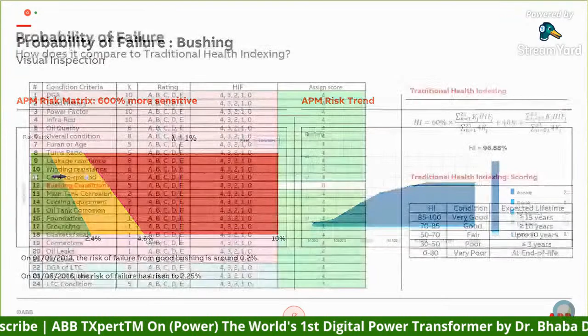So what we have done in APM, instead of a linear method, we have used a non-linear method to do the calculation. And we have made the system much more sensitive to each and every individual component in the transformer. I will give you a quick example of how it compares to the traditional health index. We are all very familiar with the traditional health index computation. I'm sure you must have seen this calculation method where we take around 24 different conditions of the transformer. We assign scores based on what we see or what we think should be the score. If you put in 0 for the bushing and 4, which is the highest score, for everything else, you will see that the traditional health index method is giving you a score of 96.88, which means the transformer is fantastic.